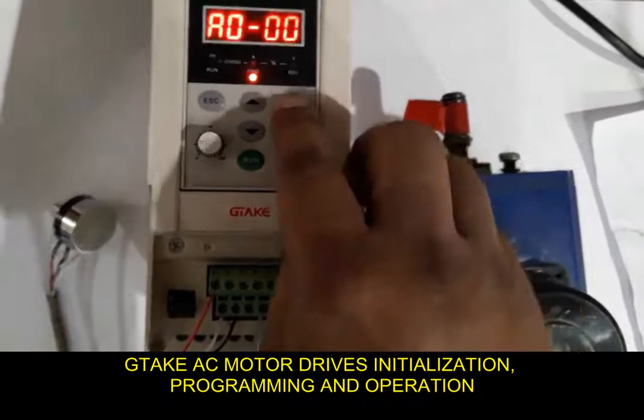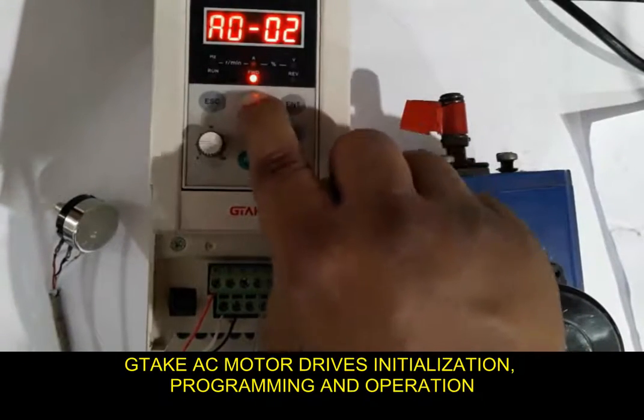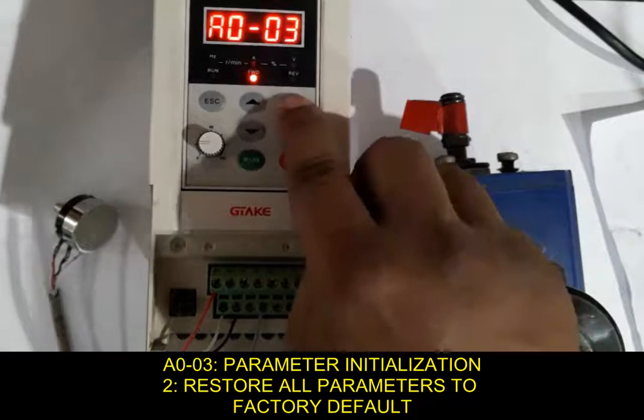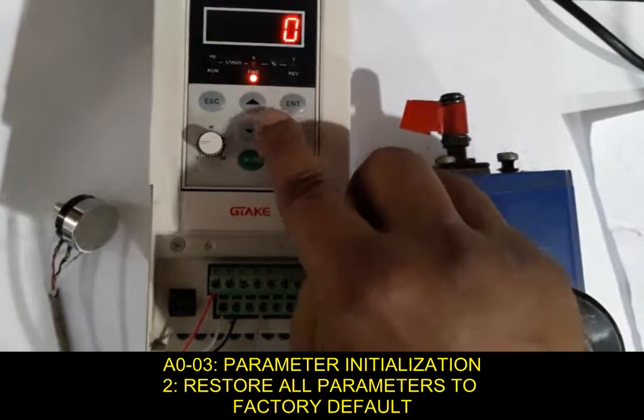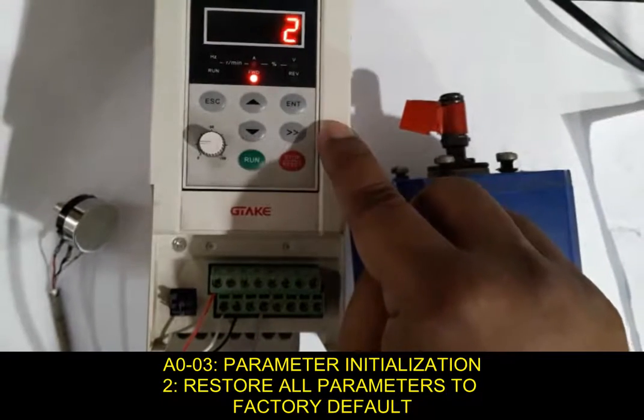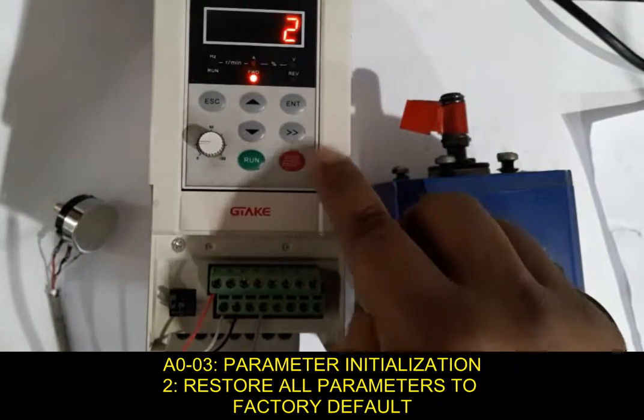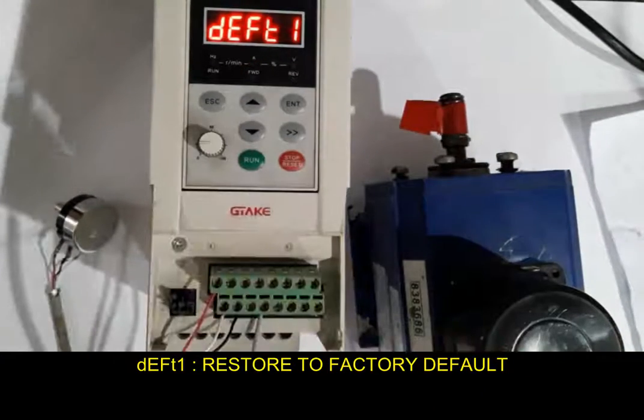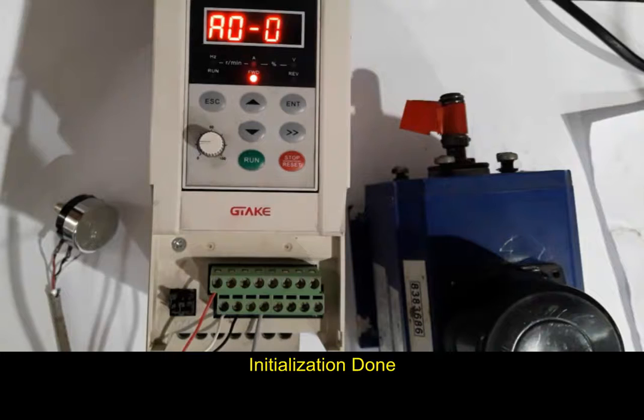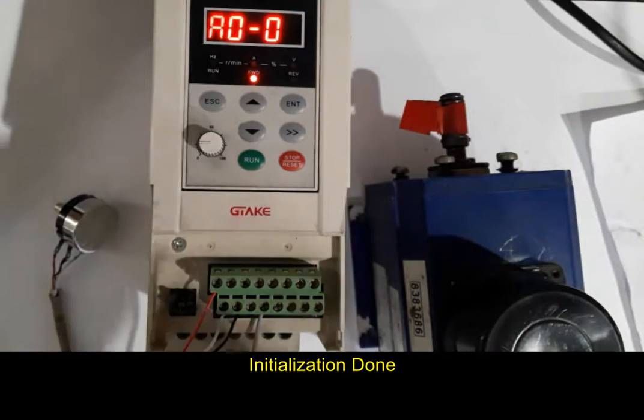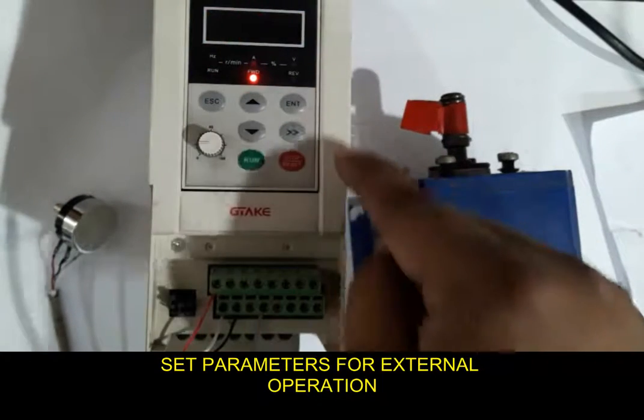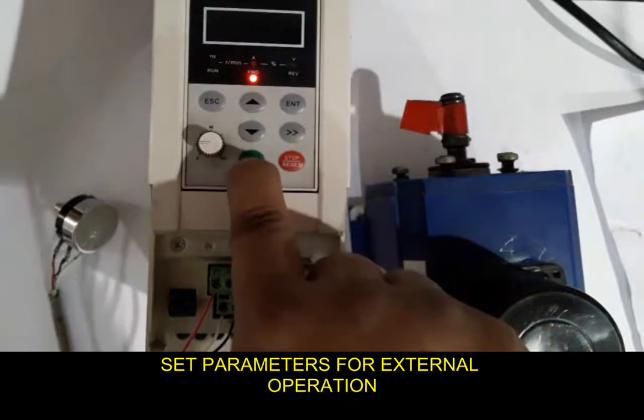Motor drive initialization, programming and operation. In parameter A003, set here 2 for all parameters initialization. Restore all parameters to factory default. The parameter is initialized. So set now external parameters for remote operation.